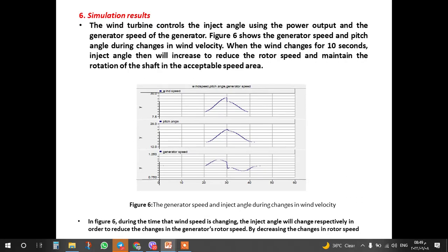The simulation results: the wind turbine controls the pitch angle using the power output and the generator speed. Figure 6 shows the generator speed and pitch angle during changes in wind velocity. When the wind changes at 10 seconds, the pitch angle will increase to reduce the rotor speed and maintain the rotation of the shaft in the acceptable speed area.